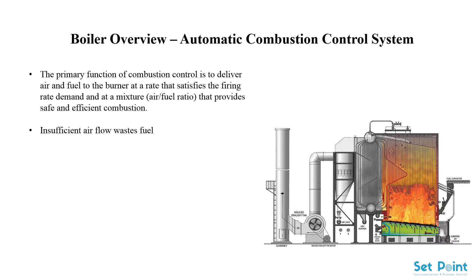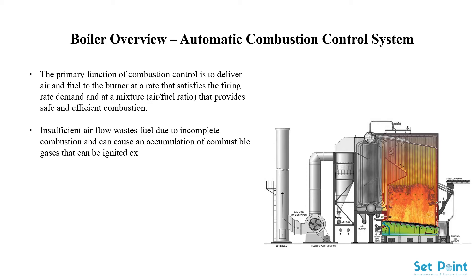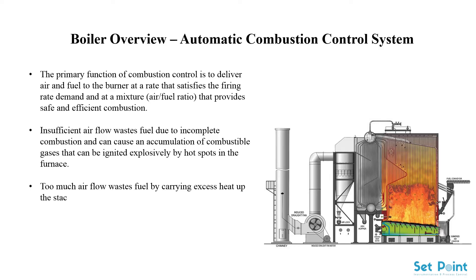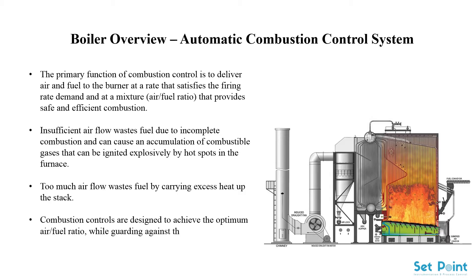Insufficient air flow wastes fuel due to incomplete combustion and can cause an accumulation of combustible gases that can be ignited explosively by hot spots in the furnace. Too much air flow wastes fuel by carrying excess heat up the stack. Combustion controls are designed to achieve the optimum air-fuel ratio while guarding against the hazard caused by insufficient air flow.